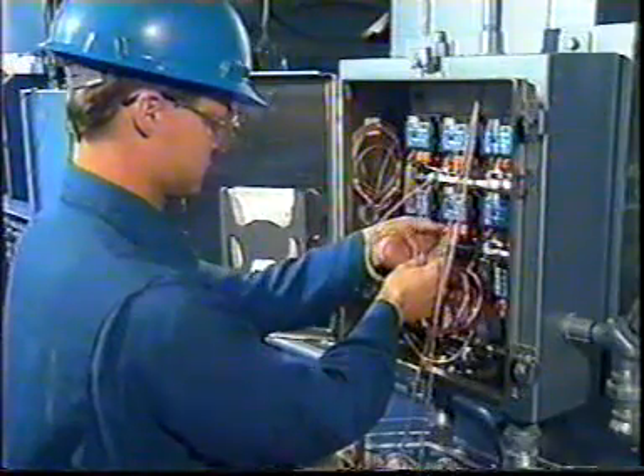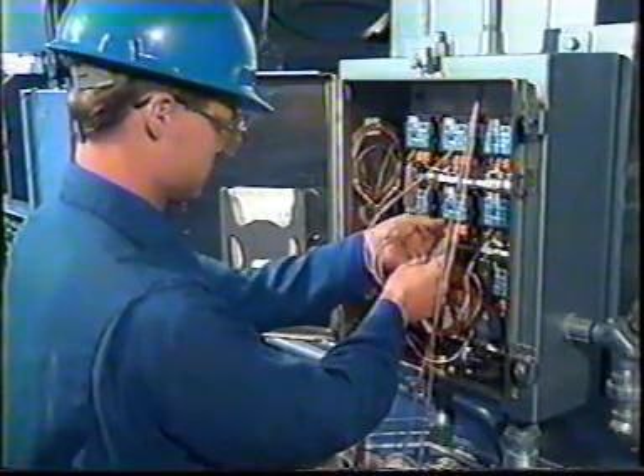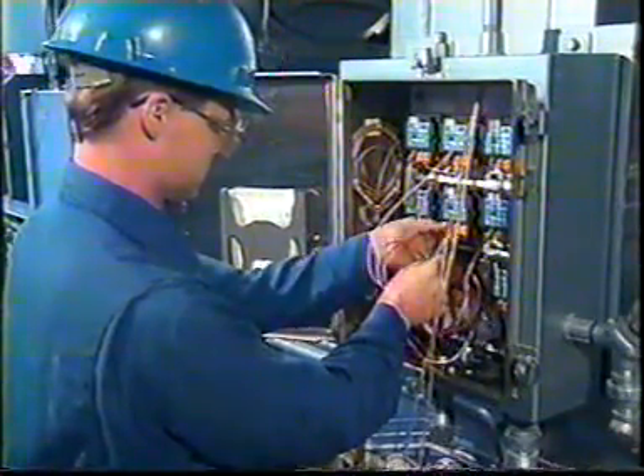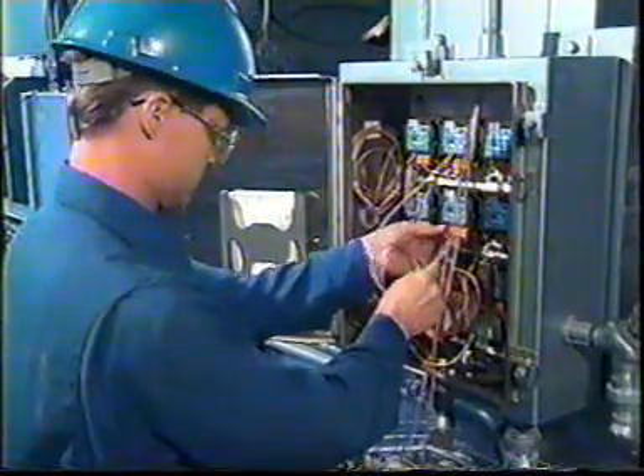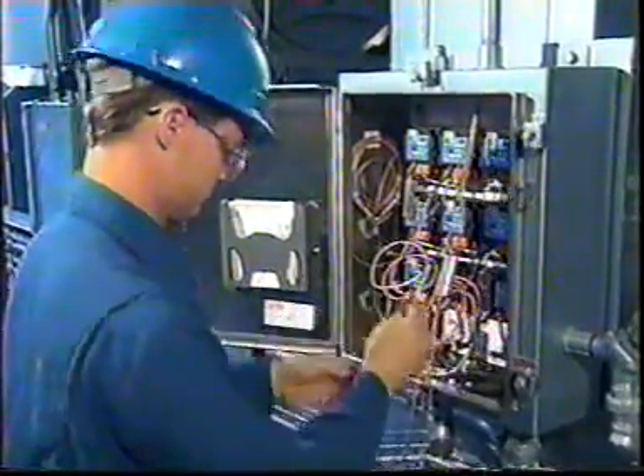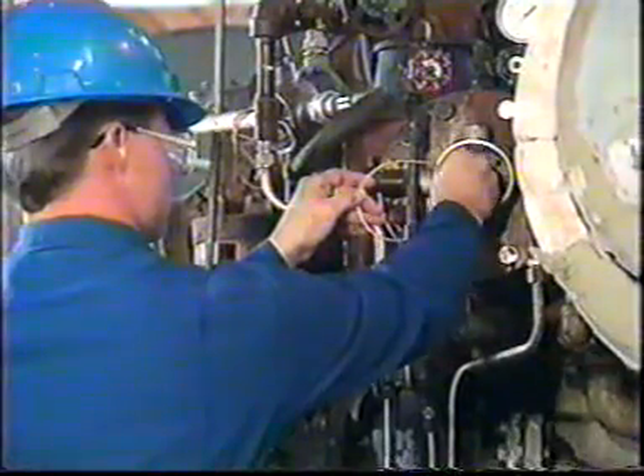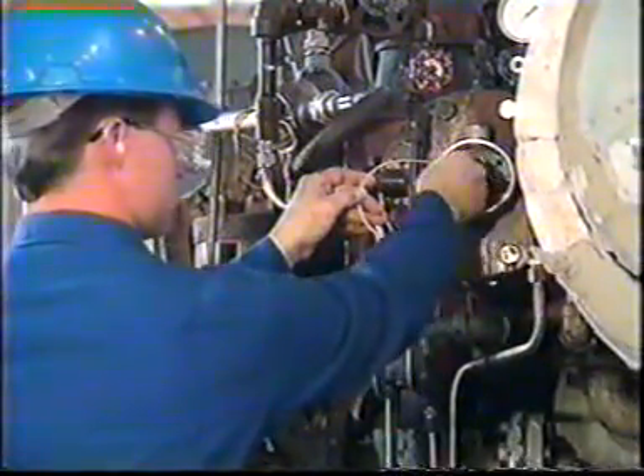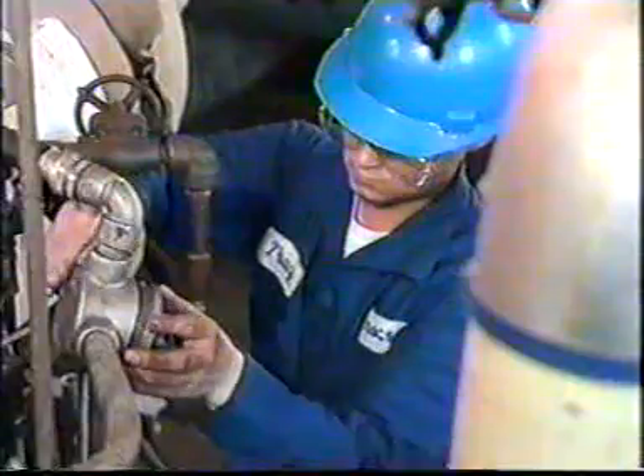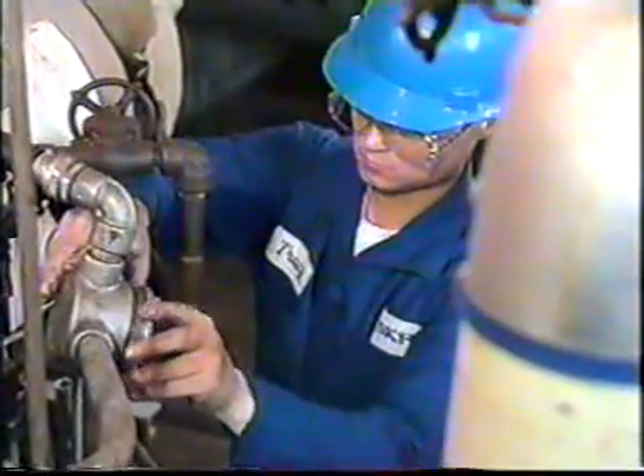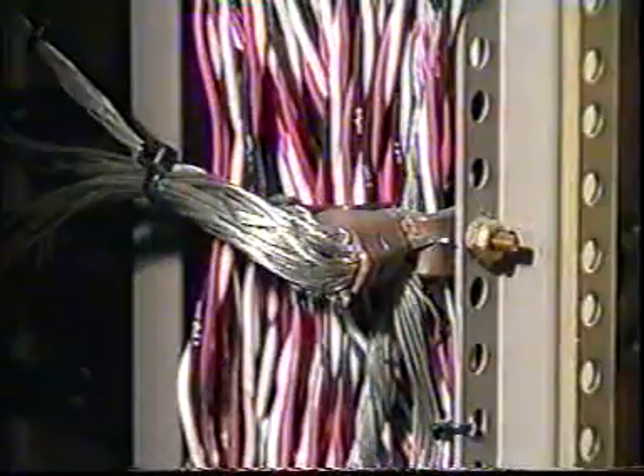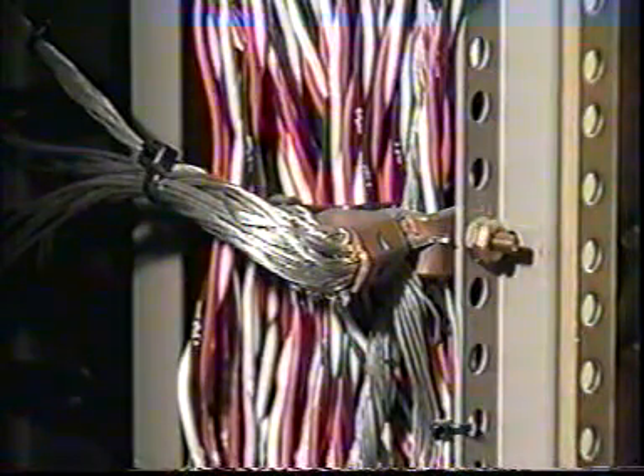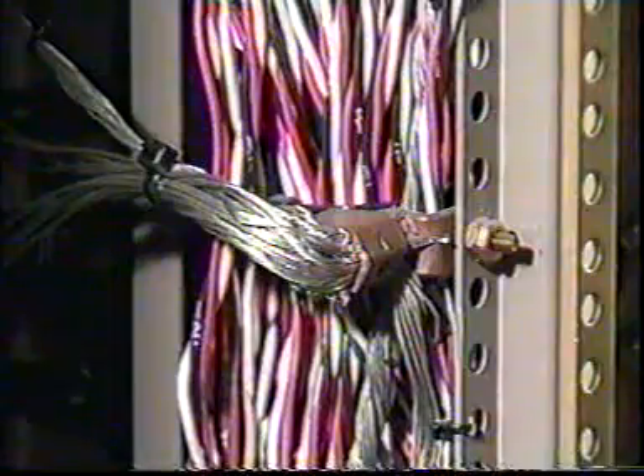Replace damaged cables. Be sure to route cables away from high-energy conductors so stray electromagnetic fields will not introduce signal errors. Ensure cables are not twisted during sensor removal and installation. Take care when closing enclosure covers to keep from pinching cables. Ground the cable in the equipment rack. This prevents signal distortion and sensing errors.